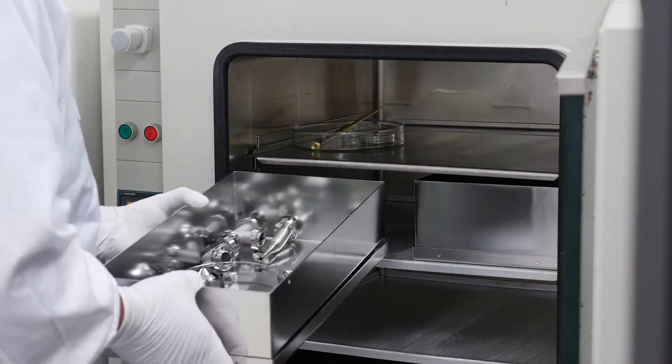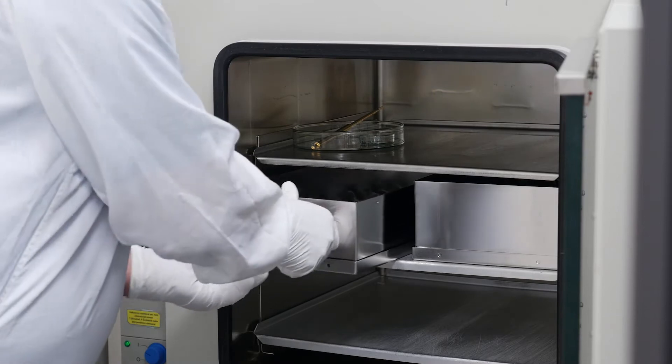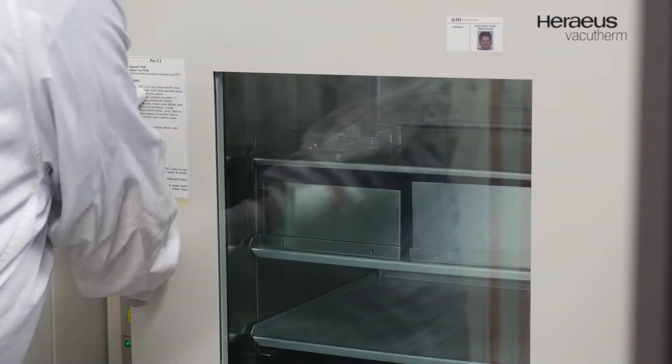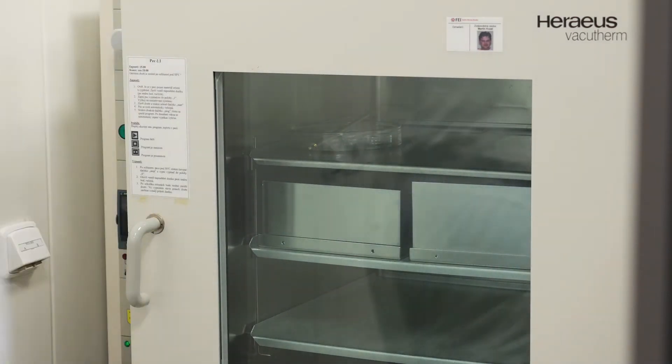To reach a working vacuum in the most complex devices, it is necessary to heat the parts to a high temperature for several hours while gases dissolved in the material are drawn out and pumped down at the same time.